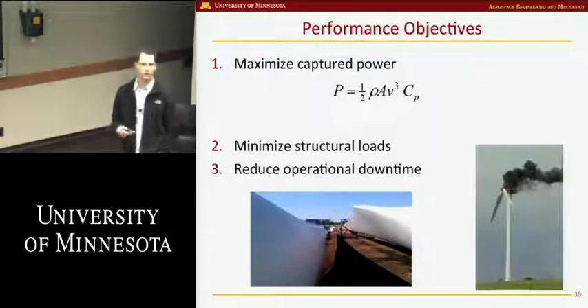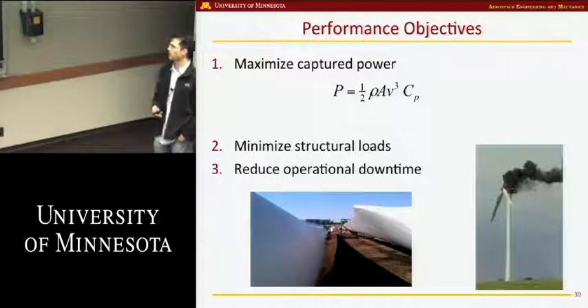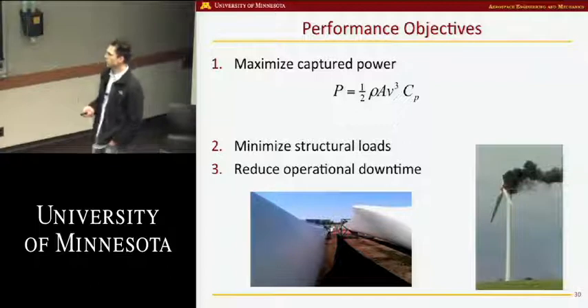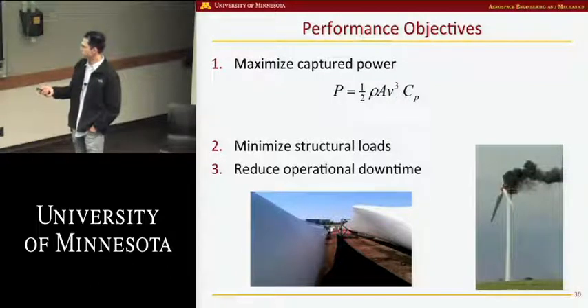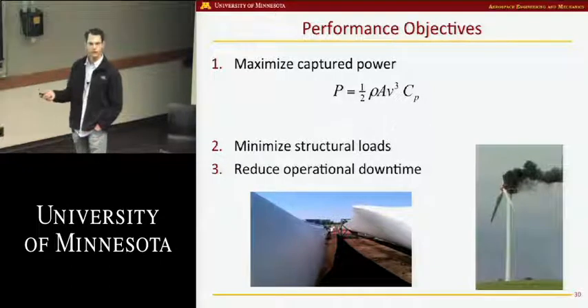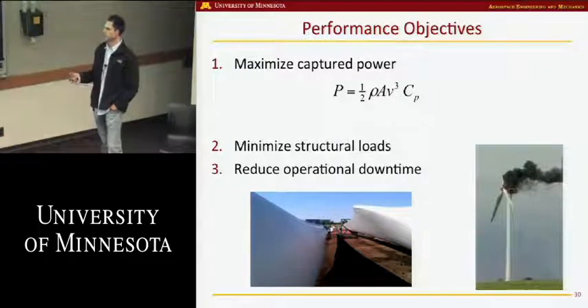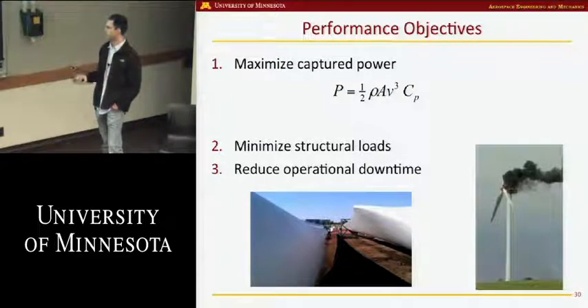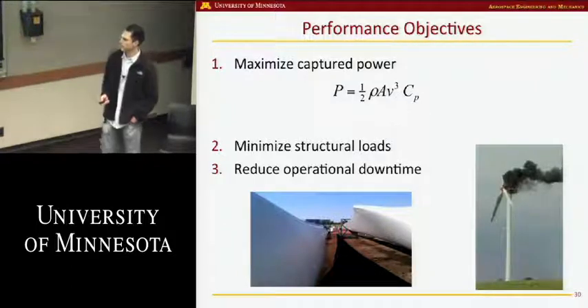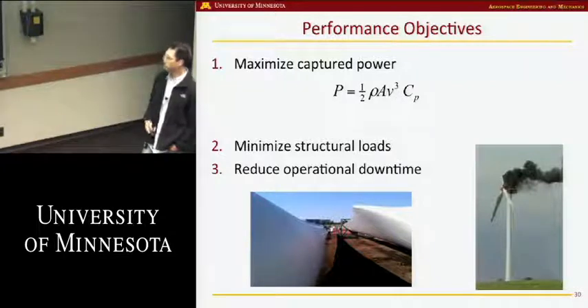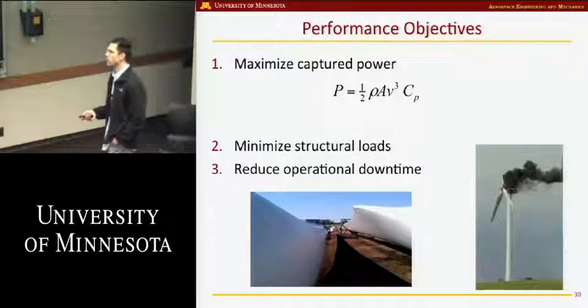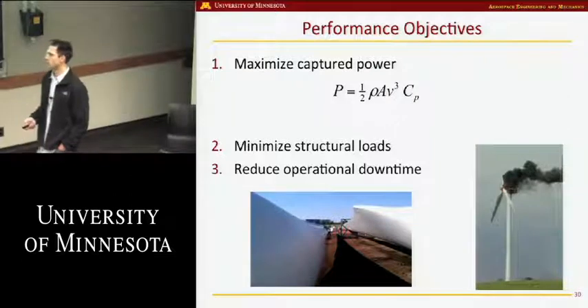There are many things you want to do with wind turbine control. First, you want to maximize the power you're capturing. But you also want to worry about structural loads — the blades are very flexible and can flop around if you're not careful, exciting blade modes and causing vibrations that do structural damage. The towers are also flexible, and poor control can excite the tower mode and cause it to oscillate. The last concern is downtime — that's the fault detection part: figuring out that something's about to break and fixing it before the turbine sits there not producing power.